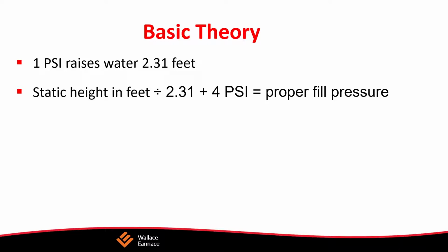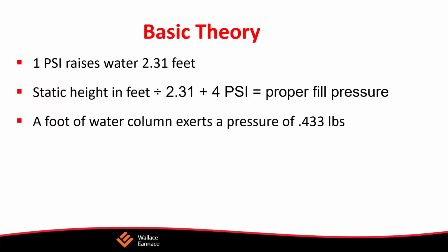If I take the static height of any building, divide that by 2.31 to get the PSI, and add 4 PSI, that is the proper fill pressure for that particular building. So if I have a house 20 feet in height, divide that by 2.31, then add 4 to that. 20 feet is going to give me about 8 PSI, add 4 to it, that's 12 PSI. That would be the proper fill pressure for a 20-foot building.